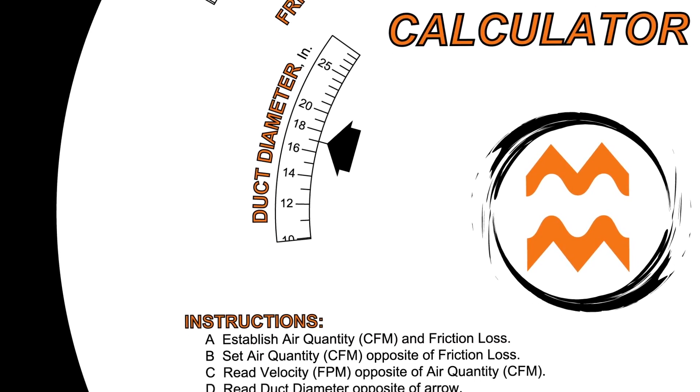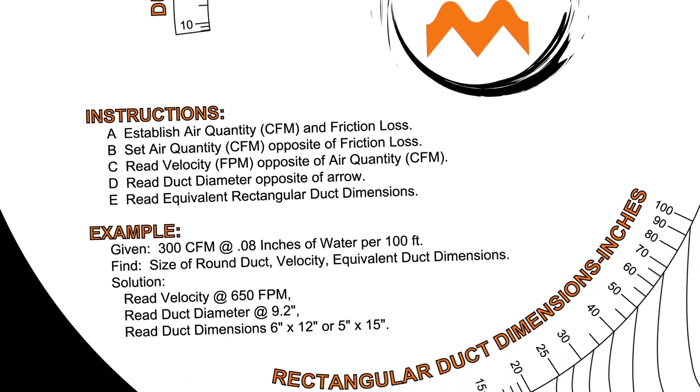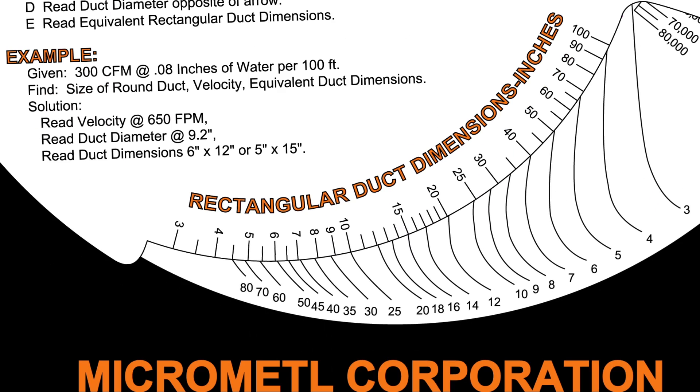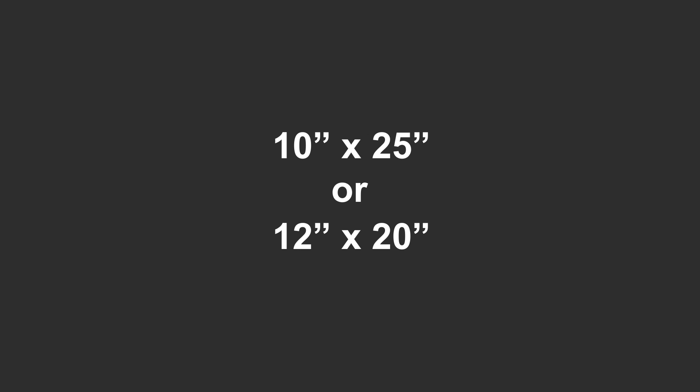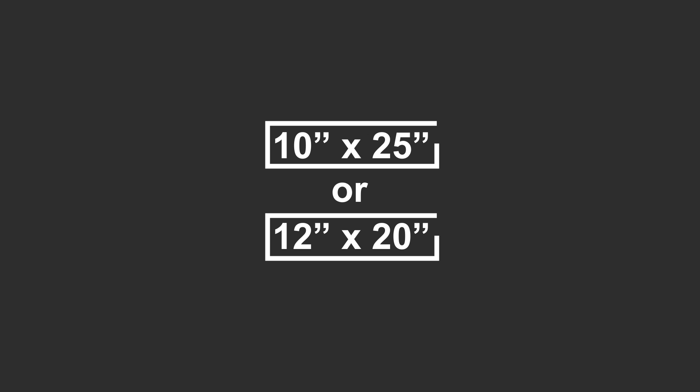Look to the bottom to select a rectangular duct size which works best in your application. Notice here, 10 aligns to 25. Additionally, 12 aligns to the number 20. Therefore, use either a 10 by 25 or 12 by 20 inch rectangular duct design and you'll get the same basic results.